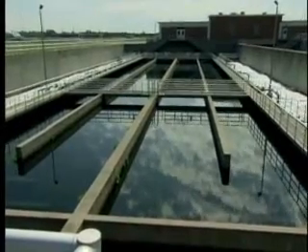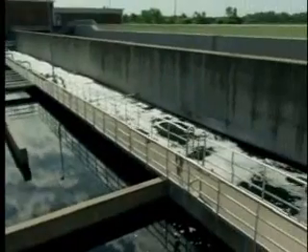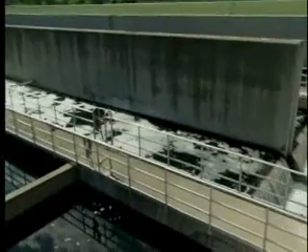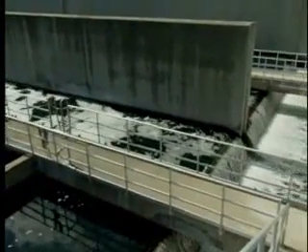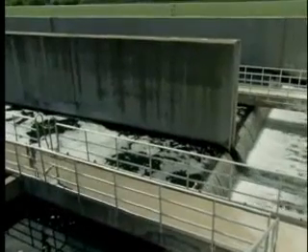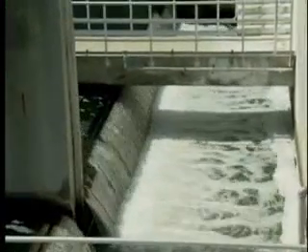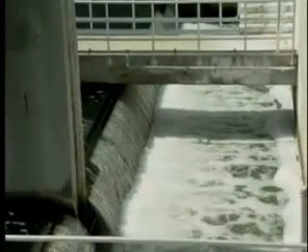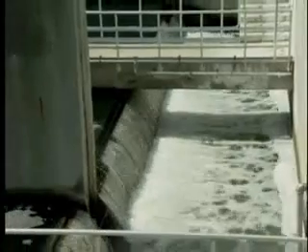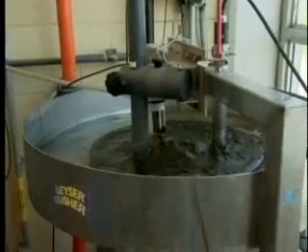In the last section of this tank, you'll see air is added. That's post-aeration. One of the requirements of the EPA is that we maintain at least 7 milligrams per liter, or 7 parts per million, however you want to look at it, of dissolved oxygen in the effluent. So we add air at the end of the process to ensure we're above that 7 milligrams per liter before it hits the river. That's our effluent.